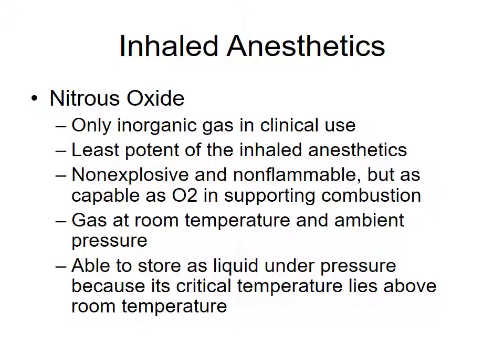Is that how nitrous works? No. No. Okay, because it's liquid in there with gas on top of the liquid. So when you're looking at the pressure, you're seeing a reflection of basically the gas that's left in there, and so it'll sit at what? Does anybody remember what the pressure is? 750, right? Yeah. And it's going to sit there, and you can think, oh, this is great, this is full, and then next thing you know, as soon as all the liquid is turned into gas, boom, there goes the pressure, and you have an empty tank. So it's liquid and gas, so it doesn't work the same way. Okay. So how do you know how much is in it? You have to weigh it. Obviously, you have to weigh it out. They might do that at whatever company it comes from.